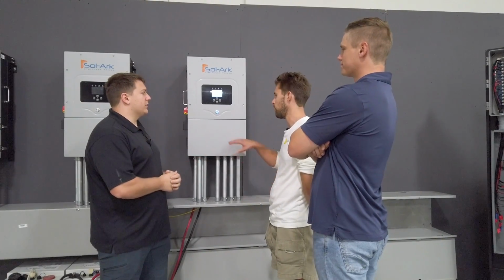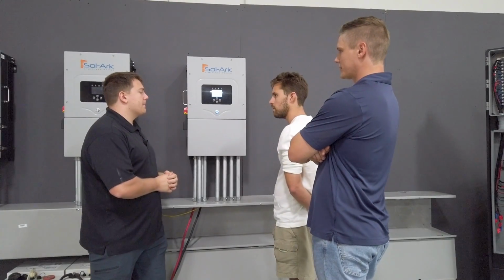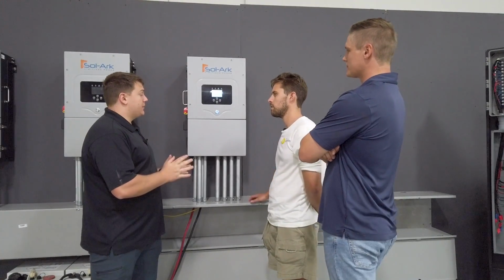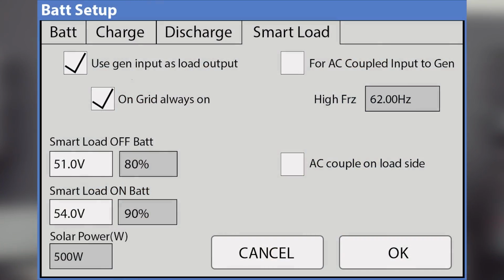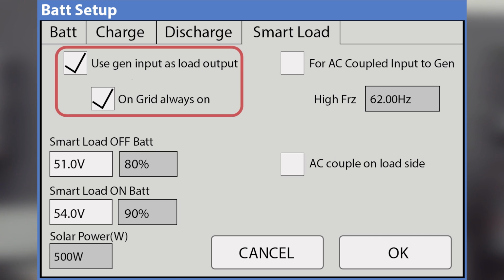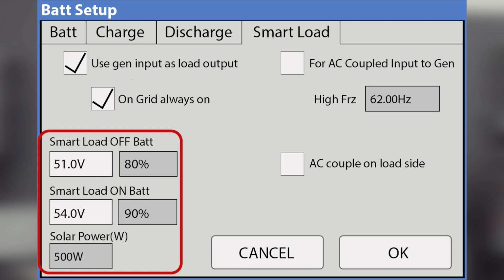Gotcha. So when the grid goes off, does it shut down that panel as well? It depends on how you program it. Over the years we've added quite a few features here. You can have it set so that when the grid's on, the gen breaker is always on, operating as a smart load output. Then when the grid goes out, depending on your settings, it'll either power it for a little bit and then turn off to preserve battery, or turn off right away, or not at all.